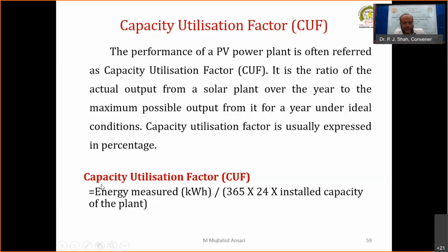Now, what is the method to calculate the CUF? CUF is the energy measured in kWh divided by 365 days, multiplied by 24, multiplied by installed capacity. Here is the 24, even though the plant does not run 24 hours; it runs effectively only 5 or 6 hours. Therefore CUF is very small, in the range of 15 to 20%. It is found that the recommended value of CUF by MERC is only 15 to 20%.